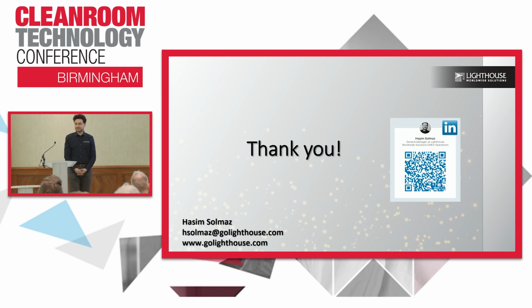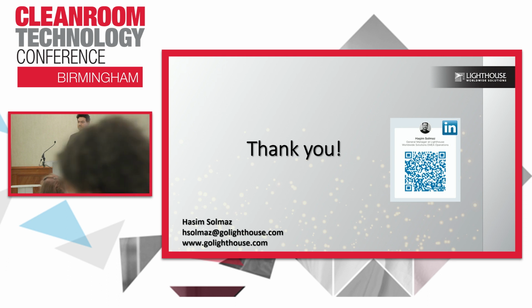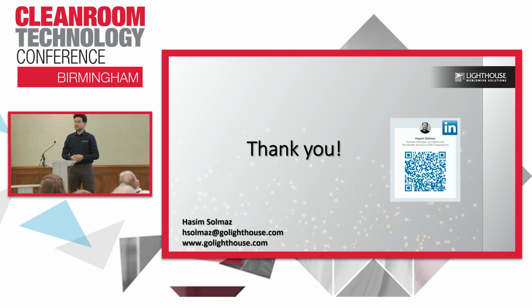Hello, David Mitchell from Biosynth. I've come across a number of auditors who, when we have looked at that 30 centimetre gap, have absolutely gone ballistic and basically said, no, do your risk assessment and work out exactly where you need it. And actually, when I've sat with them and gone through it, they've allowed me up to 45, even 50 centimetres, because they said you've got to balance the risk of where your tube is and interference as opposed to what it is you're actually trying to capture. So I just wondered where that 30 centimetres was coming from.